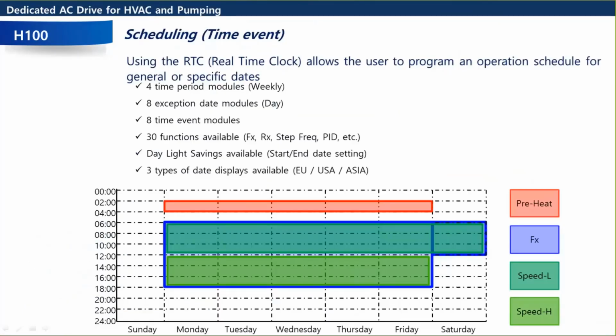Yeah, so here's that scheduling I was alluding to. Once you enable the clock, you could set up to 8 different event schedules. So you could set things to happen on certain days. You have 30 different functions that are available. FX is forward run, RX is reverse run. Then there's step frequencies, there's PID, so you could enable PID, disable PID. You could set a lower speed at night, perhaps, and a higher speed during the day. It also comes standard with daylight savings time. They call it summertime in this keypad. So you could set the drive to do the time switch automatically for you. And you could change the display, but you're probably going to want the USA display. So it's a pretty nice setup. A lot of times guys will need external timers or some kind of external equipment to run a schedule, but you could do it all in the H100 just by enabling the battery. And again, we'd recommend using DriveView9 when setting it up. It makes it a little bit easier.